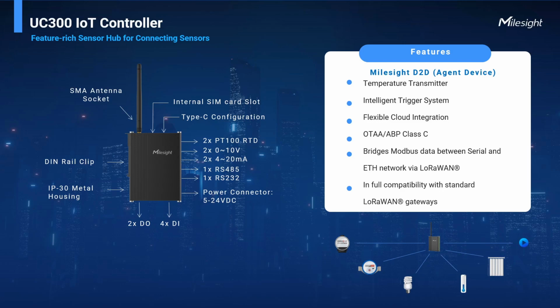This UC300 controller is LoRaWAN compatible and comes with built-in multiple industrial interfaces, input and output, to connect to conventional equipment through analog input, digital output, or serial port RS232 to RS485 interfaces, switching existing conventional systems to smart LoRaWAN applications. It also bridges Modbus data between the serial port and Ethernet port via LoRaWAN, can be easily and quickly configured by NFC port, and is DC powered.